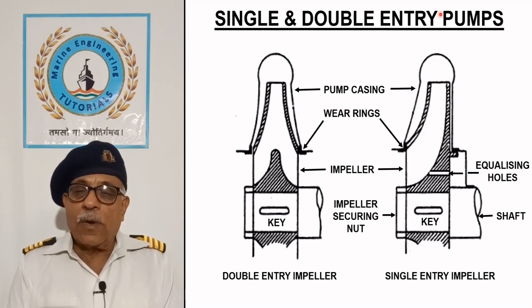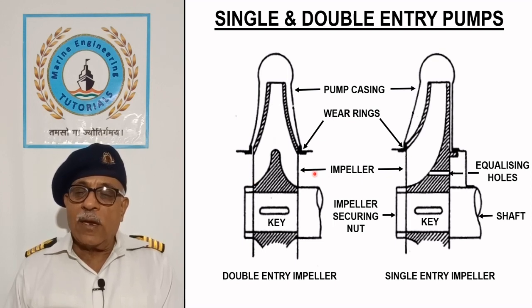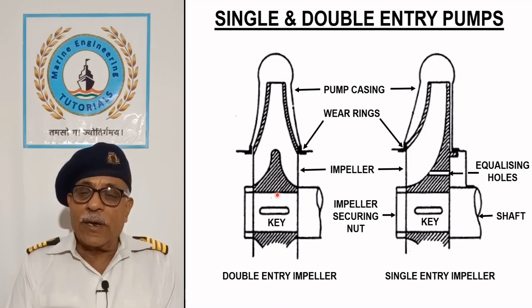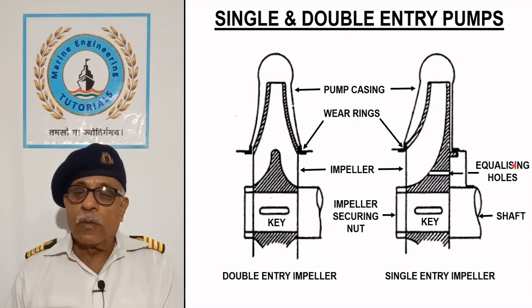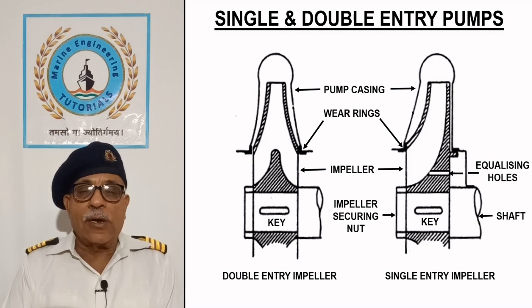Equalizing holes are not required in a double entry impeller as inlet pressure acts on both sides. The incoming liquid enters the double entry impeller from both sides and passes centrally into the volute casing for discharge. It is like arranging two pumps mounted side by side on the same shaft and working in parallel. Use of a double entry impeller increases the discharge capacity and balances the axial thrust.